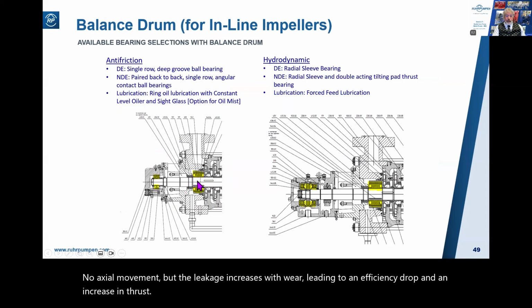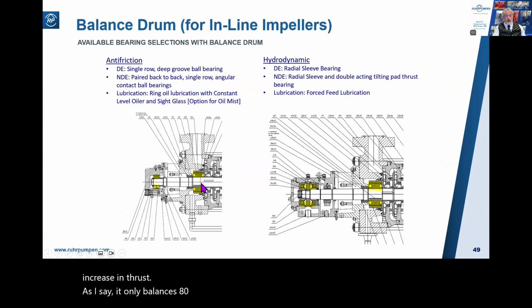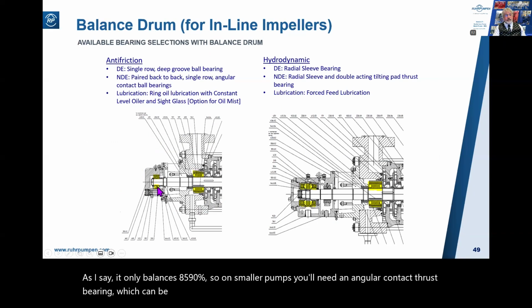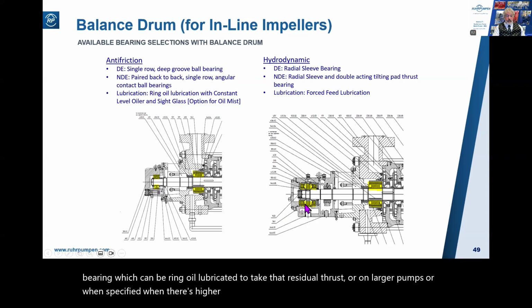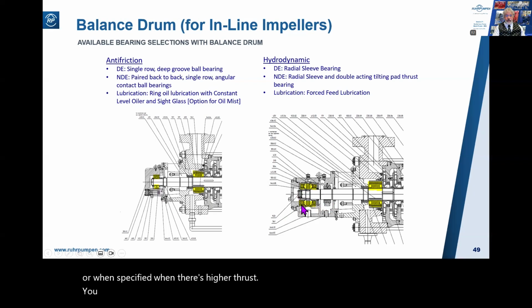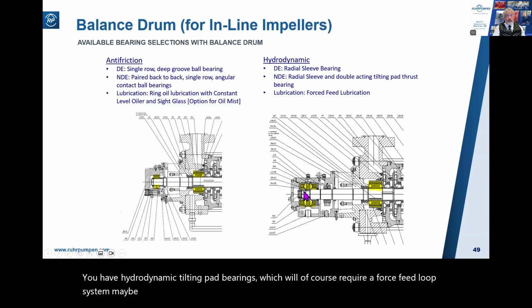As I say, it only balances 85 to 90%, so on smaller pumps you'll need an angular contact thrust bearing, which can be ring oil lubricated to take that residual thrust. Or on larger pumps, or when specified, when there's higher thrusts, you have hydrodynamic tilting pad bearings, which will of course require a force feed lube system, maybe to API 610, maybe API 614.